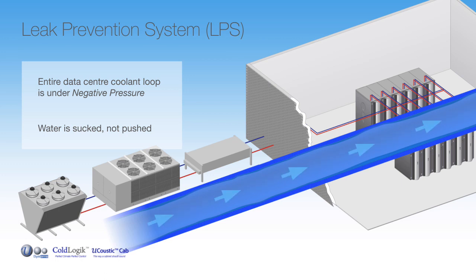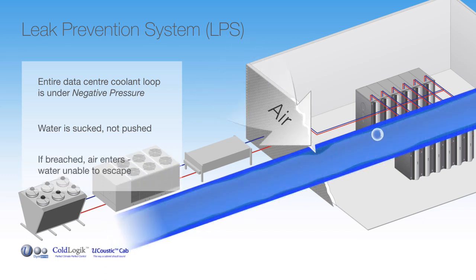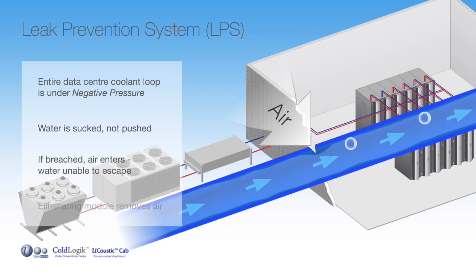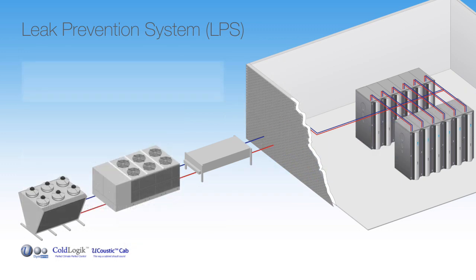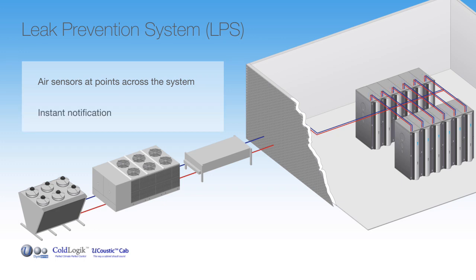In the event that a flow or return pipe is drilled into, or even in the unlikely event that a connection becomes loose, water is unable to escape. Small quantities of air are sucked into the perforation, which is then pulled along to an air-eliminating module, prohibiting any loss of coolant. Strategically placed sensors in the pipework pick up the presence of air in the system and instantly send a message to the ColdLogik management system, which in turn notifies the data center manager, all without interruption to the cooling process.